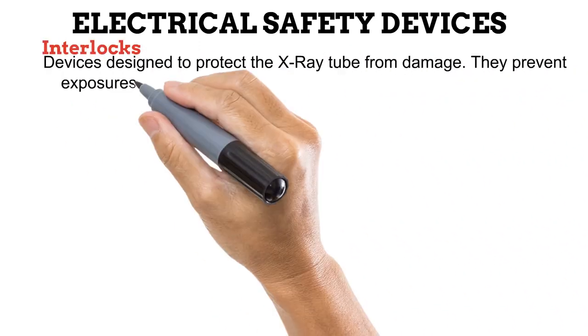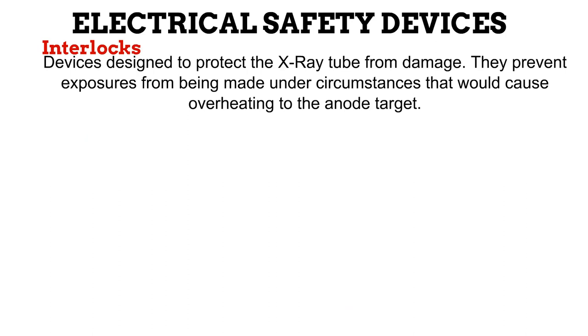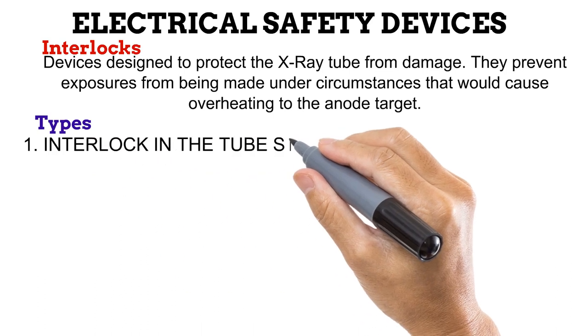We have looked at fuses, switches, and circuit breakers, which all help protect X-ray unit equipment from electrical damage. Even though these safety devices do a very good job, they do not do enough to protect the X-ray tube — and X-ray tubes are not cheap. This is where interlocks come in. They are designed to protect the X-ray tube from damage by preventing exposures from being made under circumstances that would cause overheating to the anode target. Three common interlocks connected to the X-ray tube are as follows.